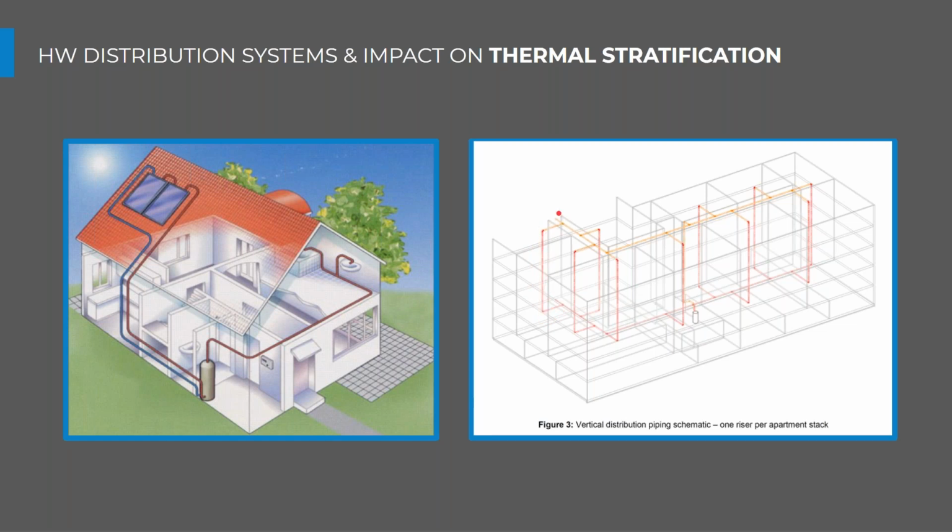as it goes up. So with these larger multifamily buildings with larger distribution systems and a lot of architectural freedom, we often see very large temperature maintenance, hot water circulation loads. So we have to be conscious, we have to be aware of that when we're designing to treat that load along with the primary heating load.